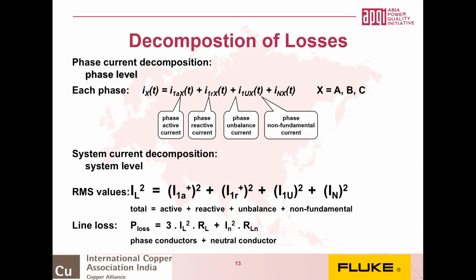The resistive load in that case is the local distribution cable. The factor of 3 is because we have 3 phase conductors. However, there is also a neutral line which can carry current. It should ideally be 0, but it may not be, and that will also cause I squared R losses in the neutral conductor resistance, and that will also appear on your electricity bill. So the complete calculation that we present is: power loss is equivalent to 3 times IL squared times RL, that's the phase conductor resistance, plus the neutral current squared times the neutral conductor resistance.